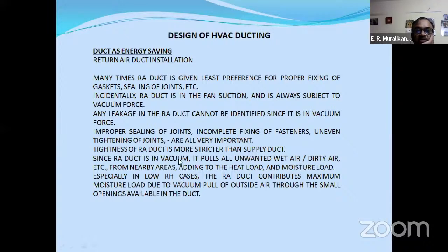Since the return air duct is in vacuum, it pulls all unwanted wet air, dirty air, etc. from nearby areas, adding to the heat load and moisture load. Especially in low RH areas, the RA duct contributes maximum moisture load due to the vacuum pull of outside air through small openings available in the ducts. So the return air duct has a very good potential for energy saving.